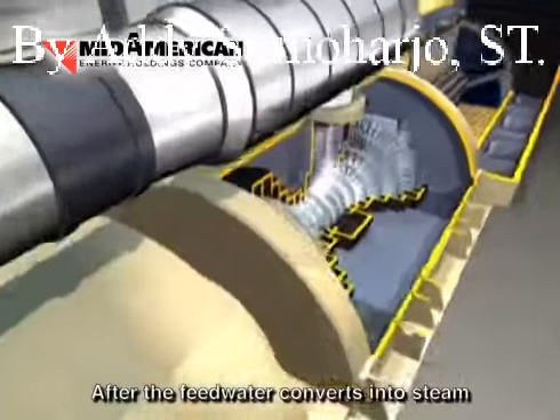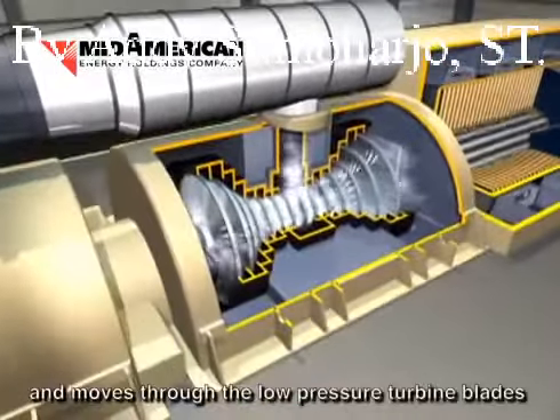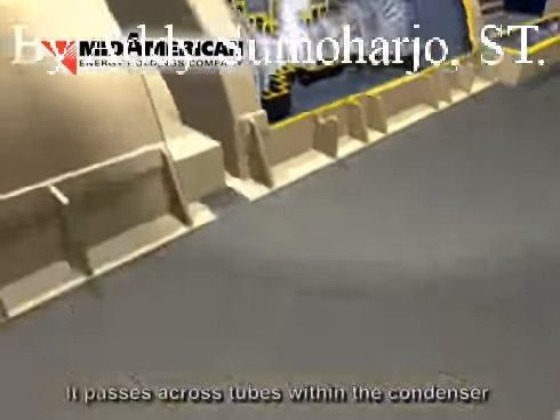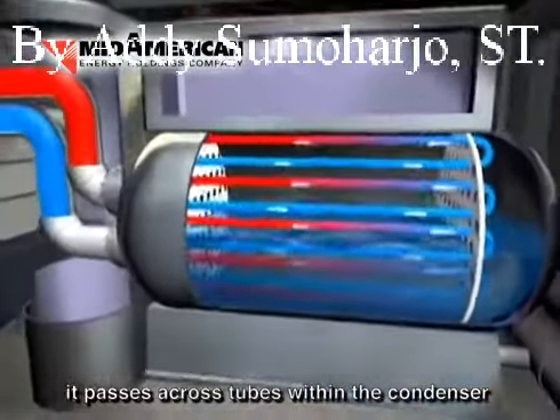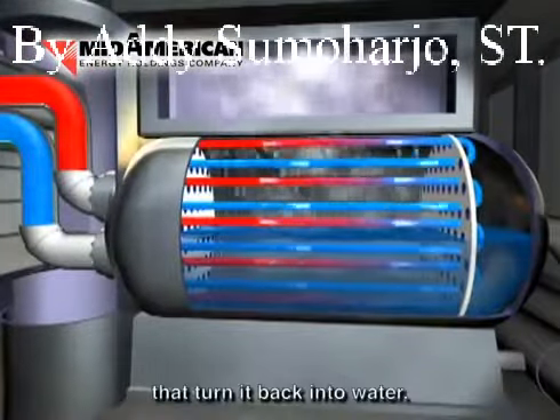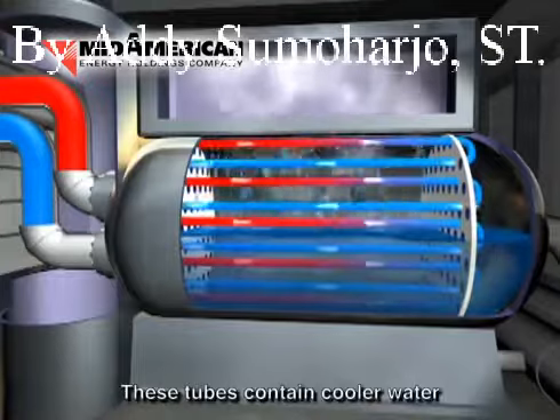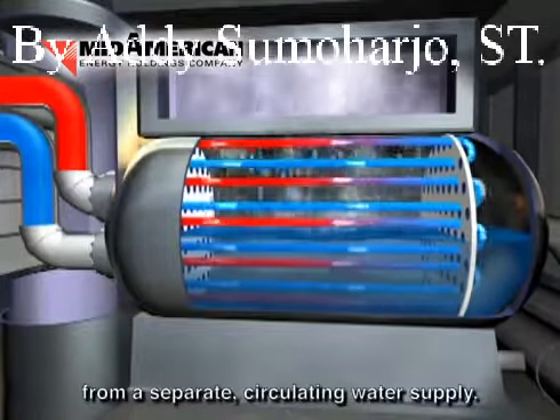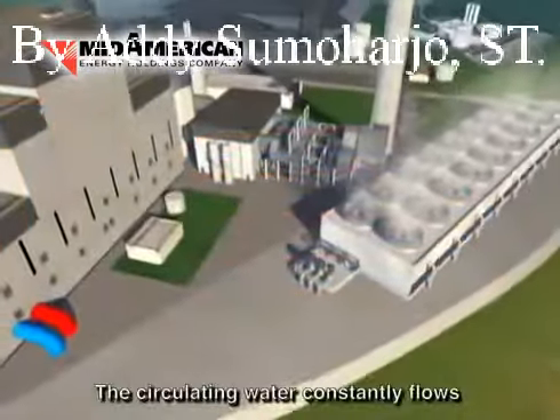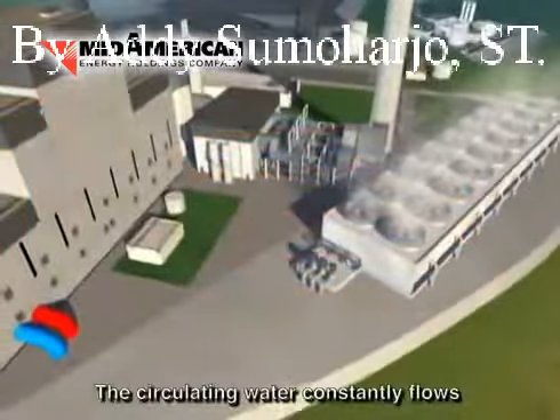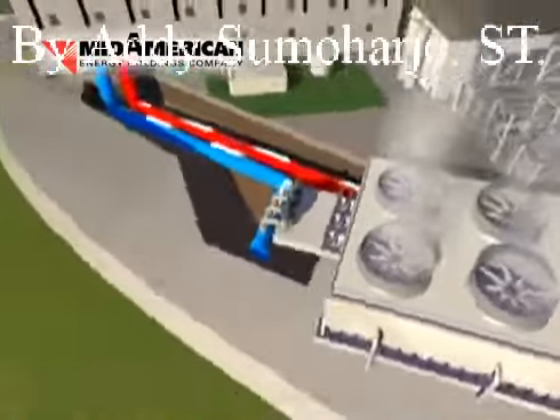After the feed water converts into steam and moves through the low-pressure turbine blades, it passes across tubes within the condenser that turn it back into water. These tubes contain cooler water from a separate circulating water supply. The circulating water constantly flows between the condenser and an external cooling tower. Fans and exposure to the air within the tower lower the temperature of the circulating water before it returns to the condenser.